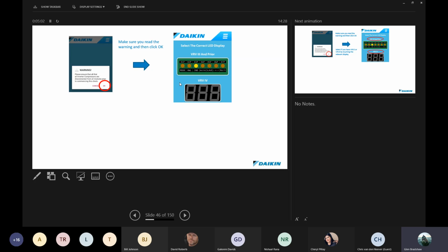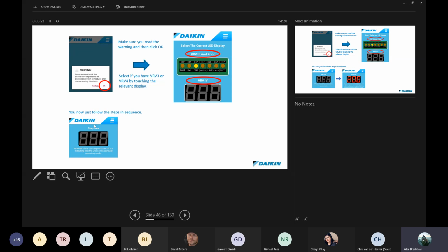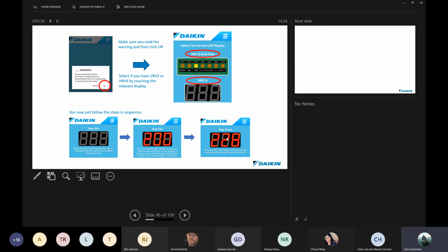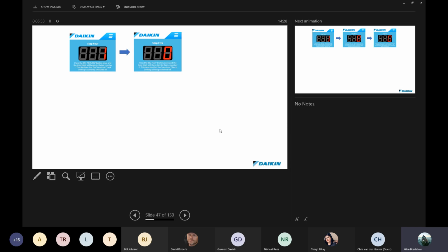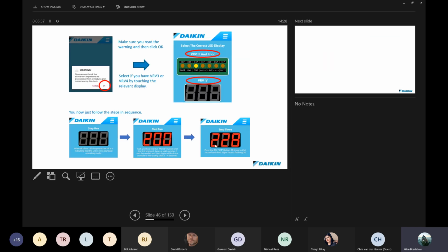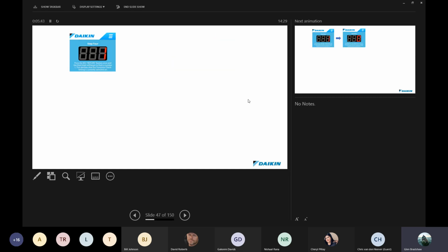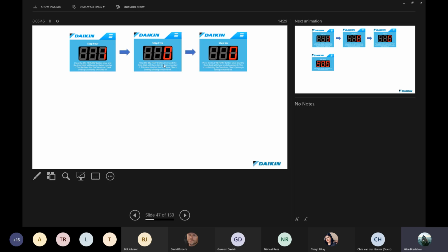Once you've accepted that, it will give you an option to choose either VRV3 and prior or VRV4 and higher. Remember, we went from the LED display to the 3-segment display in the condensing units, which makes life a lot easier. You select whichever one you want by tapping on it. Here we've tapped on VRV4. It gives you a step-by-step process as you swipe on your screen, telling you what to do, what you should be seeing, and how to make that change. Here, if you're familiar with this, we're going to mode 228. So we're now doing a transistor check mode, and we're activating that.